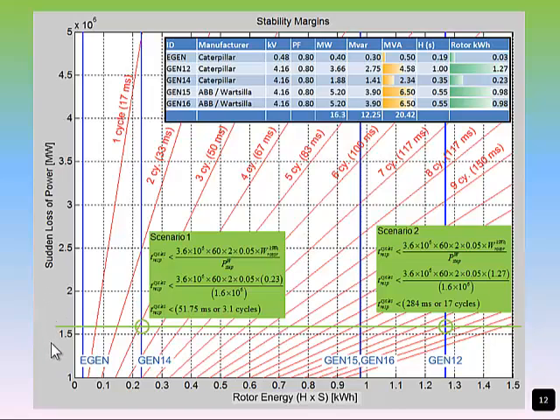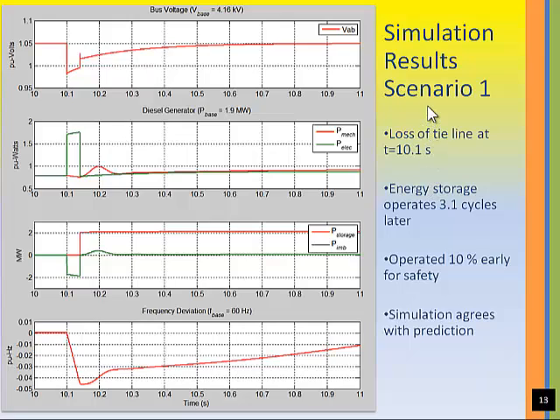We run a simulation to validate these predictions. Here are the results for scenario one. The top chart shows the generator bus voltage. We see the tie line is lost at 10.1 seconds. The generator bus voltage drops due to the power stepped onto the generator. Chart two shows the power demand as seen by the diesel machine in green. It increases due to the sudden loss of power. One can see that the governor, shown in red, does not respond immediately. According to this simulation, it takes the governor three cycles to respond.